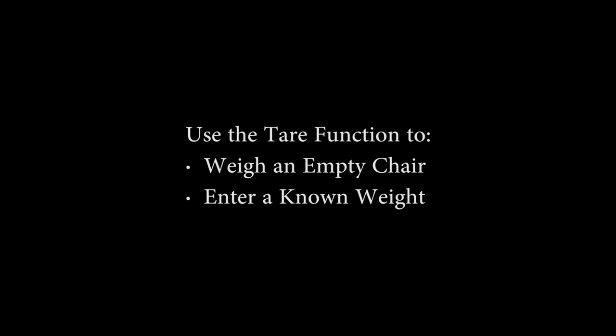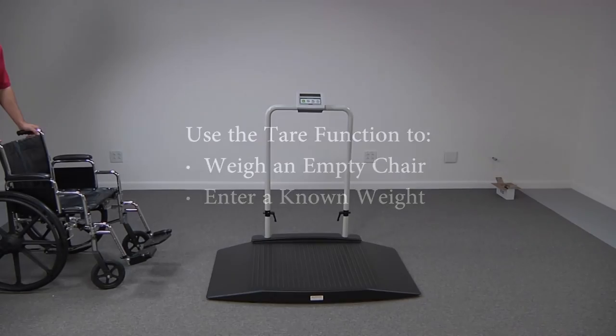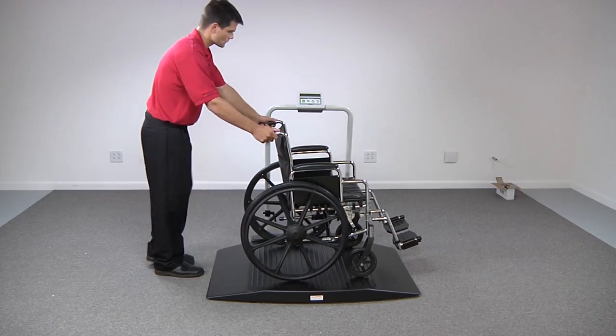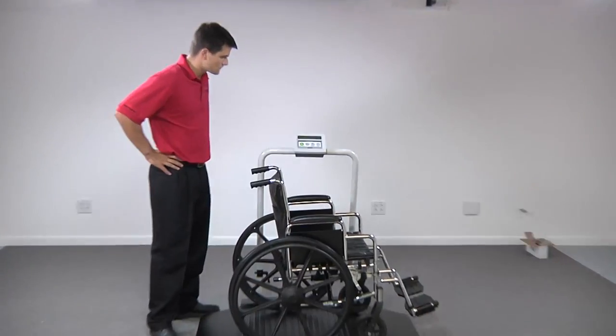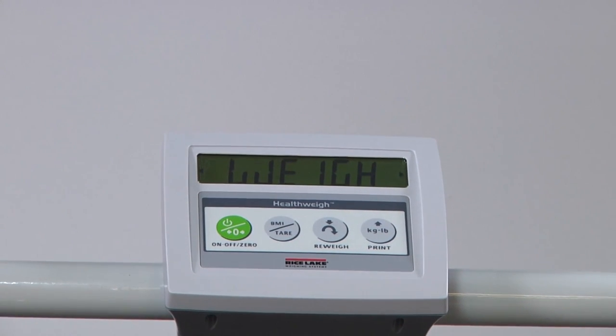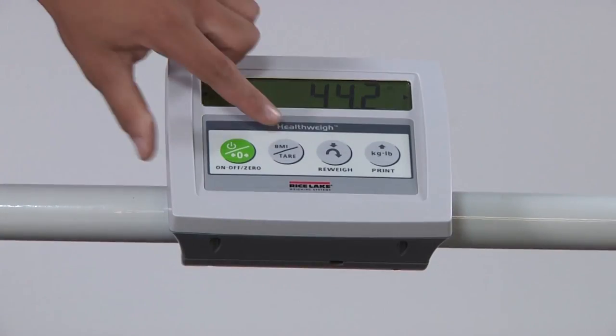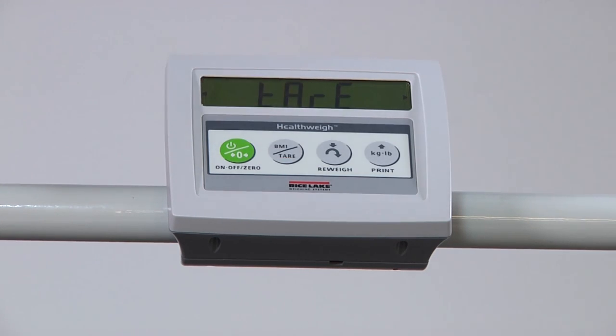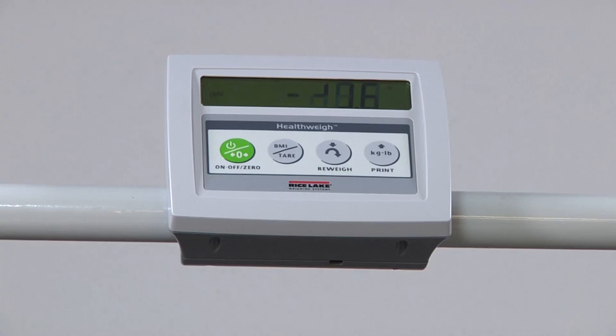To find an unknown tare, with the scale set at 0.0, place the wheelchair or extra items on the scale. The scale will weigh the items and display their total weight. With the load still on the scale, press and hold the BMI/tare key until 'tare' appears on the display. The scale will then return to 0.0 with 'tare' shown on the left side. As you remove the load, the scale reading will show a negative value equal to the weight of your items.